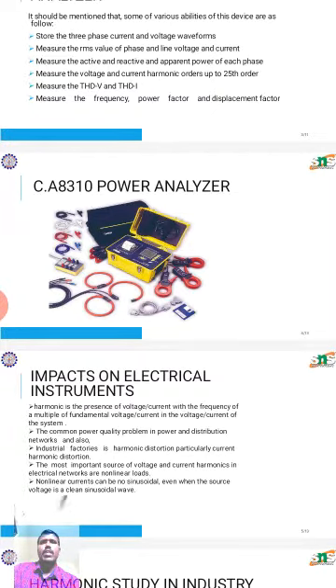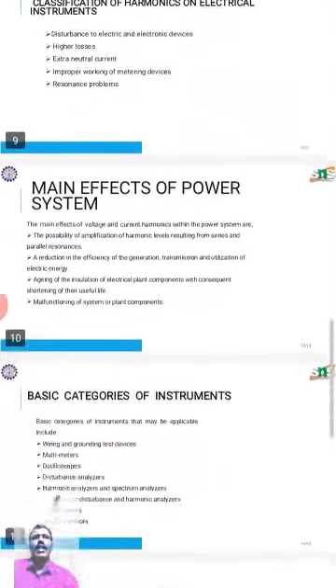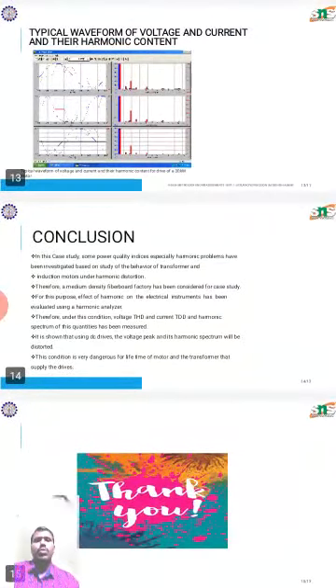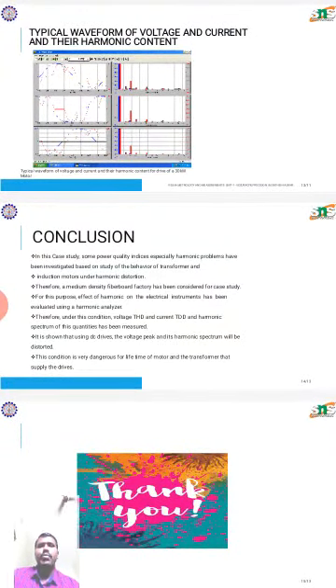The measurements show that harmonic distortion will decrease the lifetime of transformers and motors, and will also increase the losses and temperature of equipment, as shown in the given diagrams. Finally, we come to the conclusion. In this case study, the power quality indices, especially harmonic problems, have been investigated based on the behavior of transformers and induction motors under harmonic distortion.